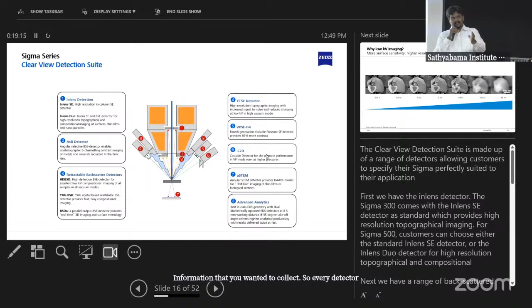So the positional accuracy of the detectors is also very, very important, because I did mention the acceleration voltage, or the energy of the beam, starting with just 20 electron volts. Imagine if the detectors are not positioned at the right angle, you will start missing the information that you wanted to collect. So for every detector, secondary electron, backscattered electron, chemical composition analysis using EDS, or your Auger electron detector, whatever you name it, the positional accuracy is very, very important. And that's why many times when you see an electron microscope, especially from Zeiss, they look bulky. They look huge. The chamber looks huge because we take samples on the scale of centimeters. Why do we need such a big microscope? It's all because of the need for positional accuracy of these detectors.